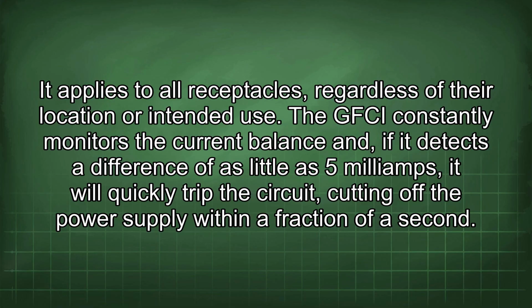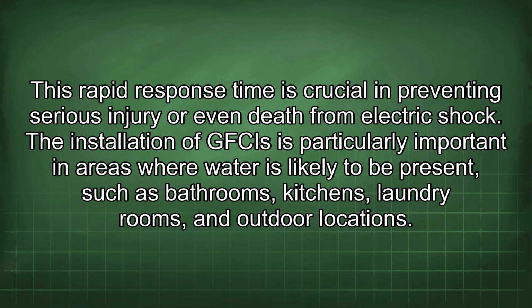The GFCI constantly monitors the current balance, and if it detects a difference of as little as 5 milliamps, it will quickly trip the circuit, cutting off the power supply within a fraction of a second. This rapid response time is crucial in preventing serious injury or even death from electric shock. The installation of GFCIs is particularly important in areas where water is likely to be present, such as bathrooms, kitchens, laundry rooms, and outdoor locations.